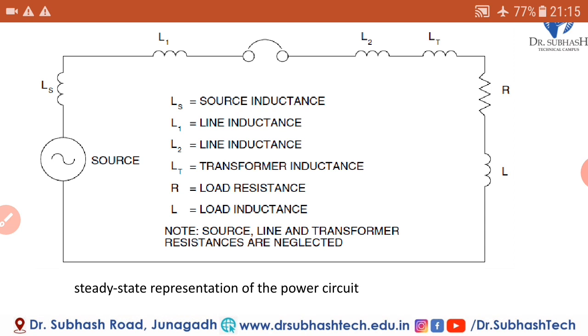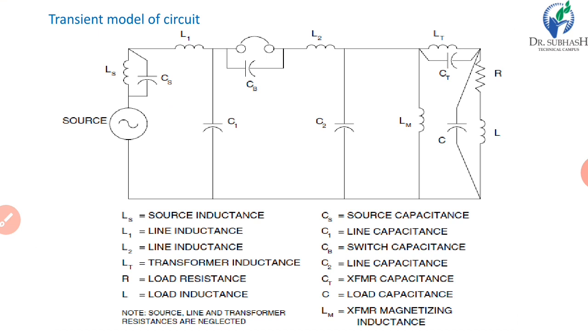Next, we will see the transient model. This is the transient model of the circuit. Here we can see the source capacitance CS placed across the source inductance Ls. Here also one capacitance, line capacitance C1, is added. Switch capacitance CB is placed across the circuit breaker. Then one more line capacitance is there. LM stands for the magnetizing inductance of the transformer.